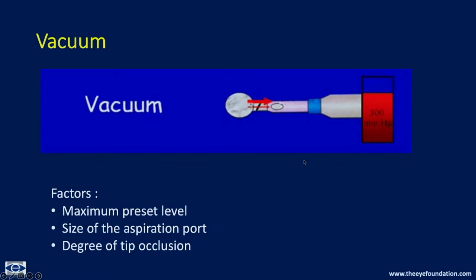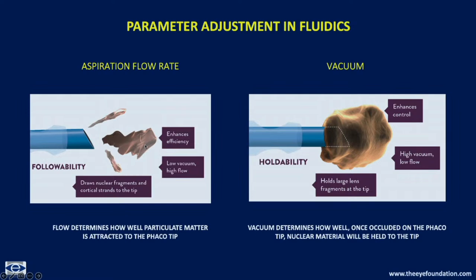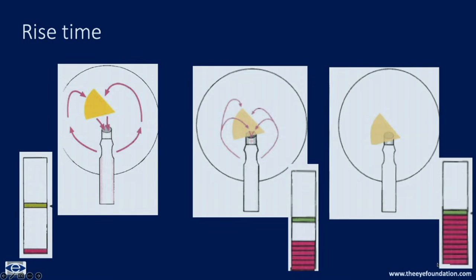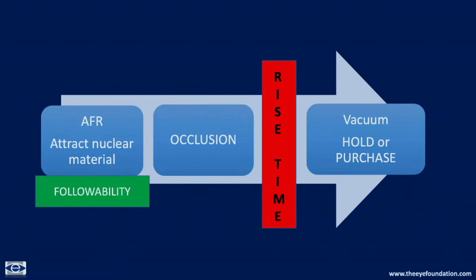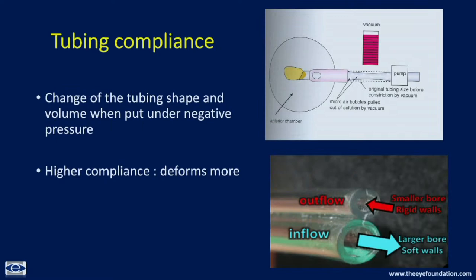Vacuum builds once occlusion is maintained with the peristaltic pump - since no more fluid enters, but the rollers keep moving, a negative pressure builds in the phaco probe giving you the vacuum or hold. AFR gives followability when unoccluded and pieces move toward the probe. Once the piece occludes the tip, the vacuum gives subsequent purchase over the nucleus. The time it takes for the maximum preset vacuum to build after occlusion is called rise time. AFR gives followability which brings the pieces, occludes the tip, and then the vacuum builds to the maximum preset - that interval is the rise time.